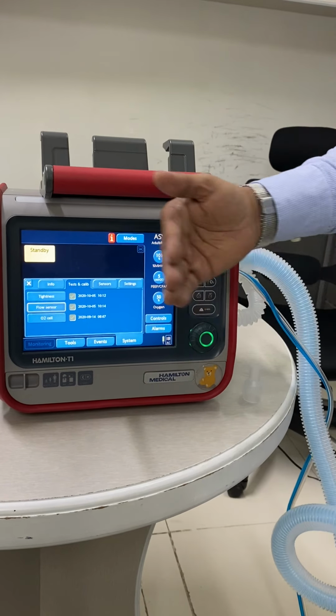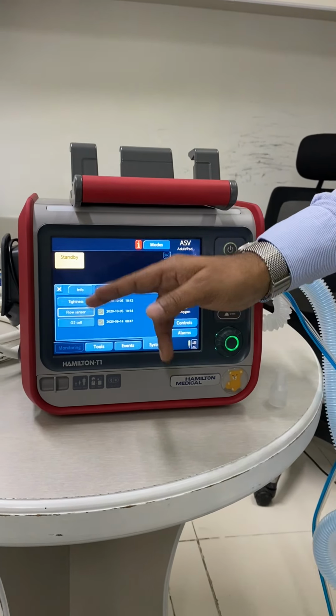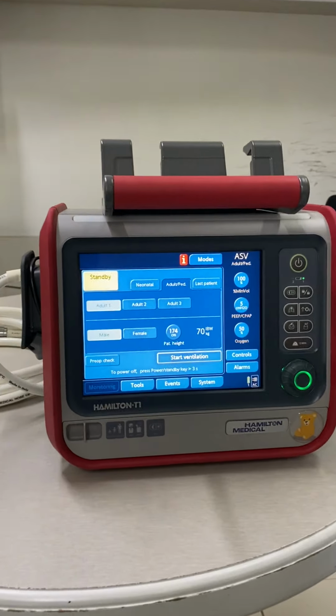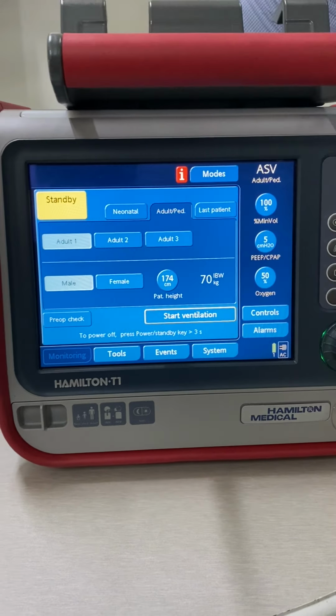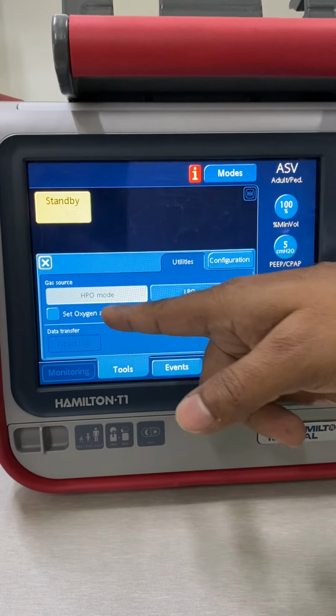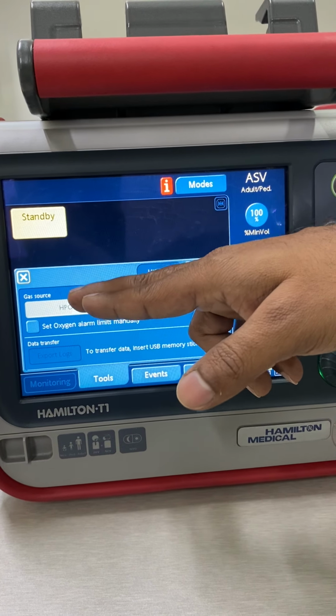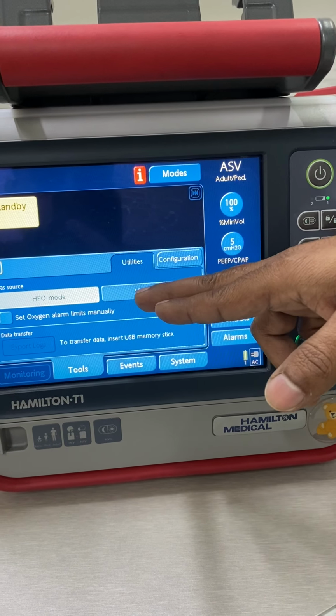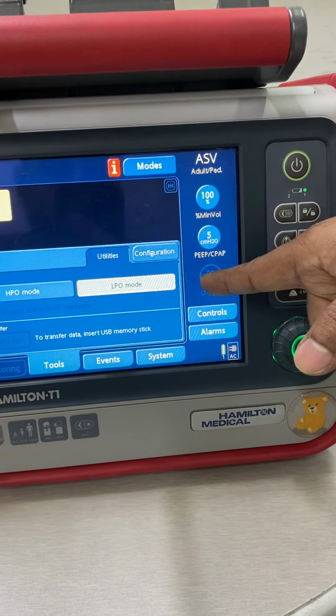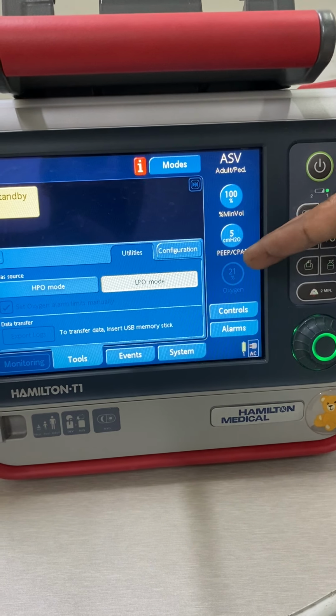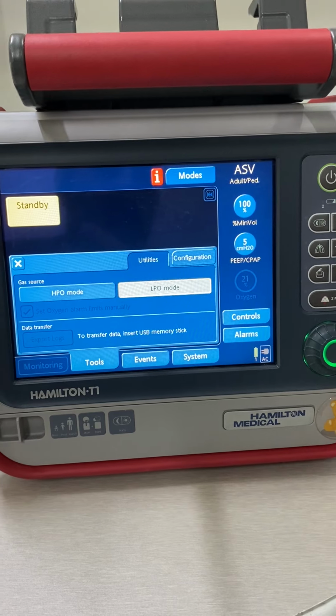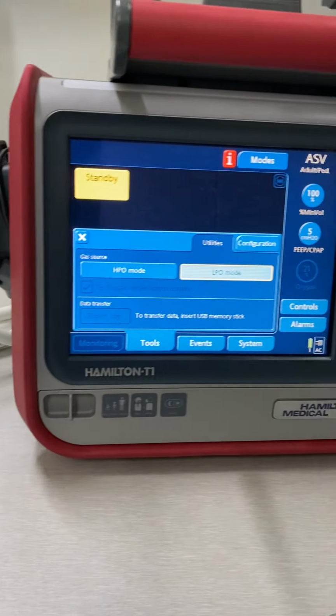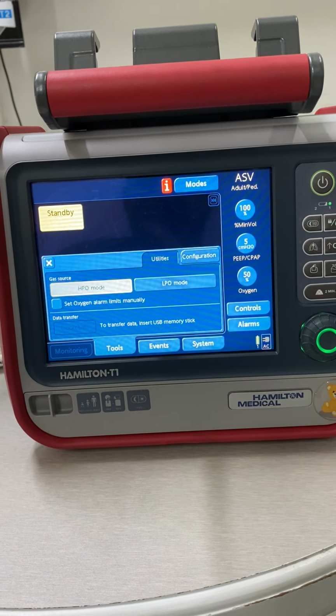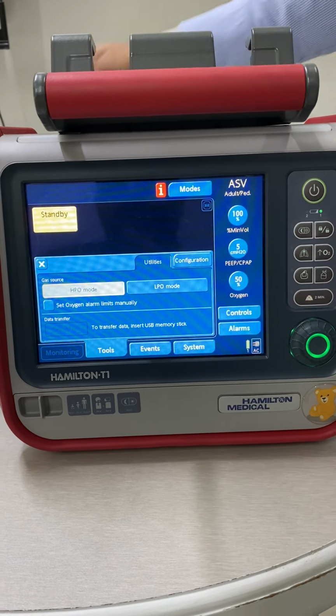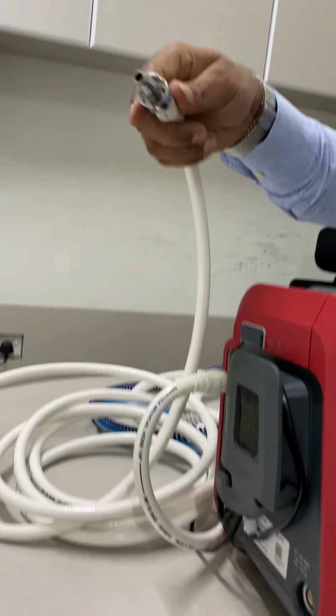O2 cell calibration, if you want to do it, takes about 2 minutes. You have to press it, it will do it by itself. Okay, at the moment I'm not doing it, and you can close it. Now you can choose the oxygen supply. If you go to the tools here, you can see HPO mode and LPO mode. HPO is for high pressure oxygen, LPO for low pressure oxygen. If you choose low pressure oxygen, you can see on the screen that the oxygen is now inactive. That means you cannot set up the FiO2 in the machine. So usually you will always be using high pressure. Only if you are running out of oxygen, you can use the cylinder with the low pressure. Otherwise, keep it on HPO mode. Then you can set up the FiO2 in the machine and connect the oxygen through the high pressure oxygen. You can connect to the central line or to the cylinder with the high pressure regulator.